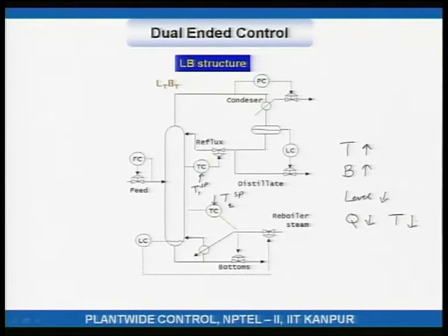Now, what that implies is the temperature is essentially getting back, because like I discussed, a change in bottoms at the same reboiler duty will take a long, long time for the tray temperature to get back. The dynamics is very slow. So, if tray temperature goes up, I want that tray temperature to get back to set point quickly.